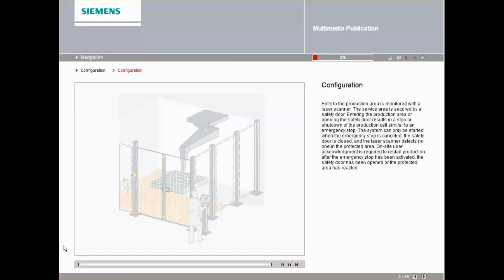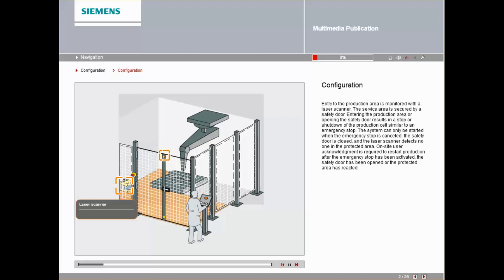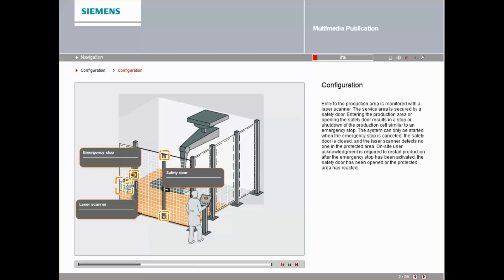The entry to the production area is monitored with a laser scanner. The service area is secured by a safety door. Entering the production area or opening the safety door results in a stop or shutdown of the production cell similar to an emergency stop.